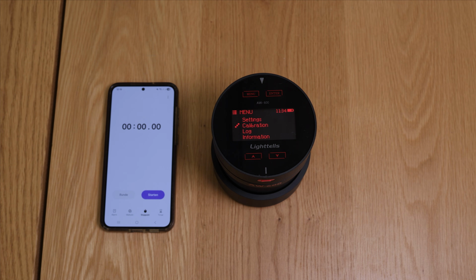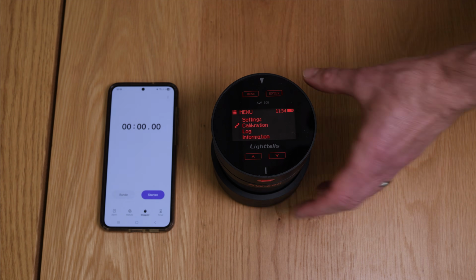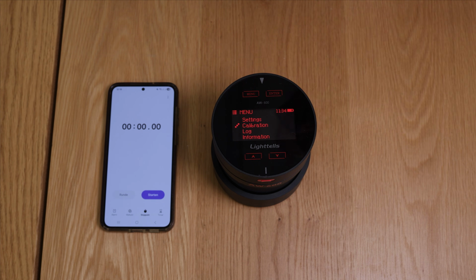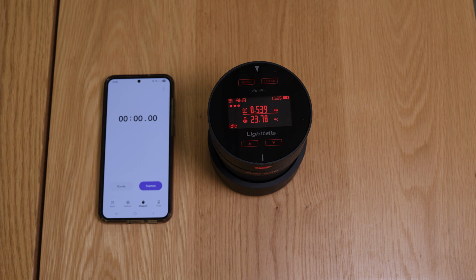So calibration is being done similarly to the OMIX Plus. You also take this saturated liquid, put it in this little cup, and put it in. I'm not going to do it now because I just did it yesterday, and it takes about 20 minutes because it's really doing this long, precise measurement. Calibration is nothing that you have to do every day, but just from time to time so that the unit is calibrated. Now it's ready for the first measurement.